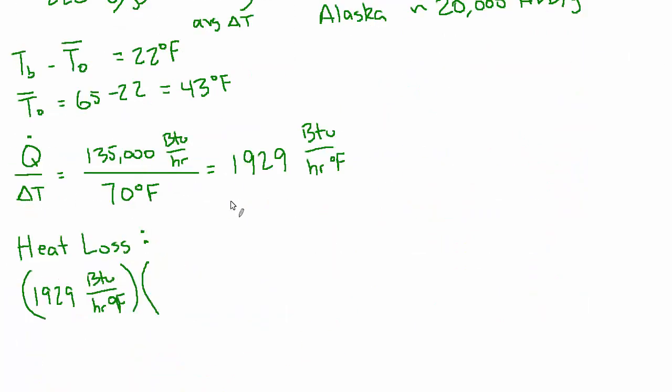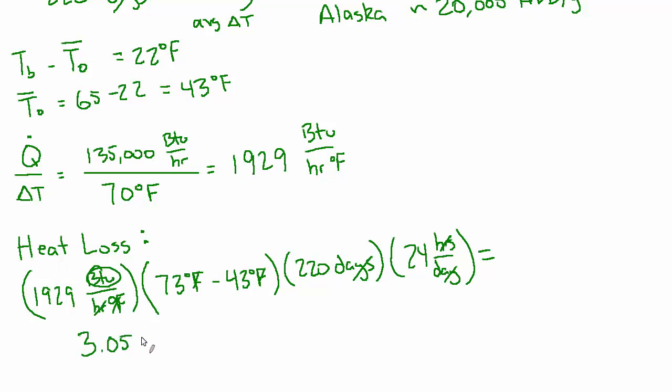The occupants have tampered with the heating controls, so they're actually running it at 73 degrees. That's the number we want to use for the inside temperature. And the average outside temperature is 43 degrees. So now our delta T is not 22, it's actually 30. It's a pretty significant difference. So that's going to get rid of degrees F. And now we want to multiply by the amount of time in the heating season, which is 220 days. And we can change that into hours, 24 hours per day. And days will go away. And hours will cancel. And we'll just be left with BTUs. And that comes out to 3.05 times 10 to the 8th BTUs. So 305 million BTUs is the total heat loss for the whole season. And that's answer A.